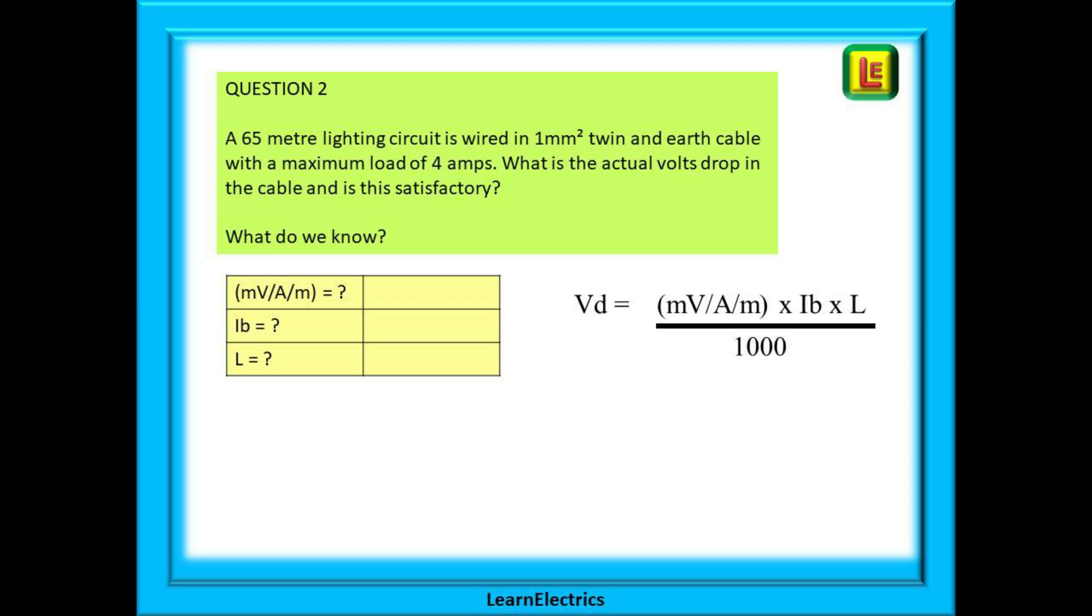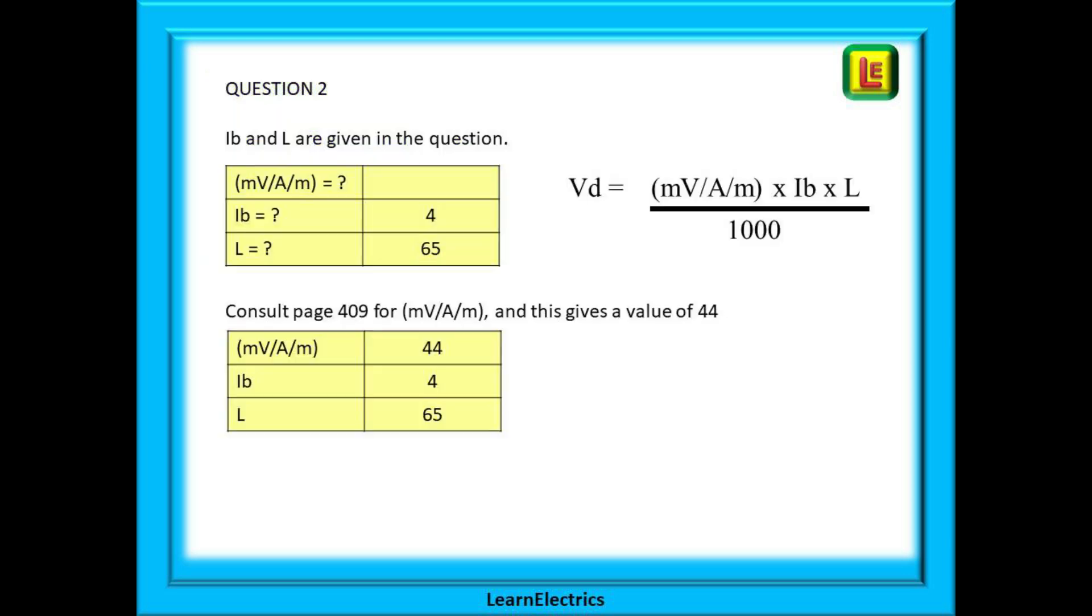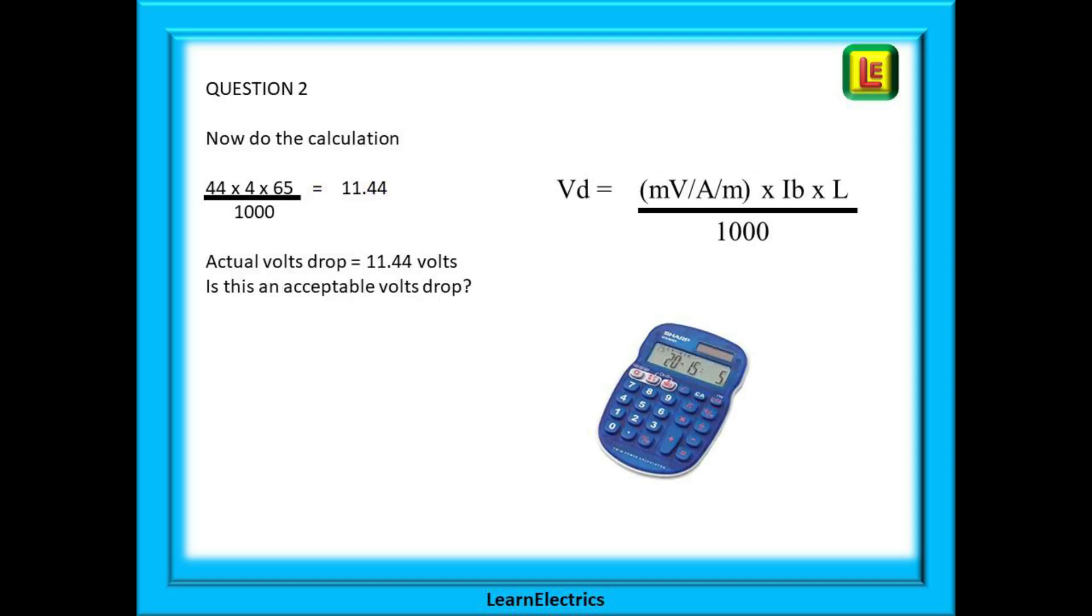Let's try another voltage drop question. A 65 meter lighting circuit is wired in one millimeter twin earth cable with a maximum load of 4 amps. What is the actual volts drop in the cable and is this satisfactory? Let's begin by writing down what we know. Ib, the current, is given in the question. The length is also given. Now look at page 409 for twin earth flat cables and find mV/A/m for one millimeter cable, and we find this is 44. Now do the calculation.